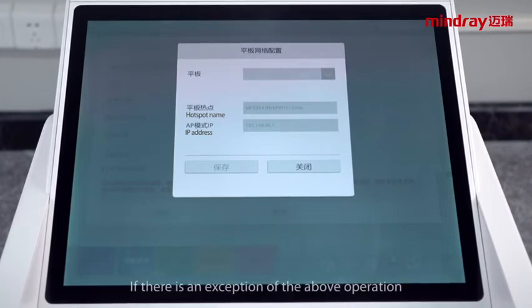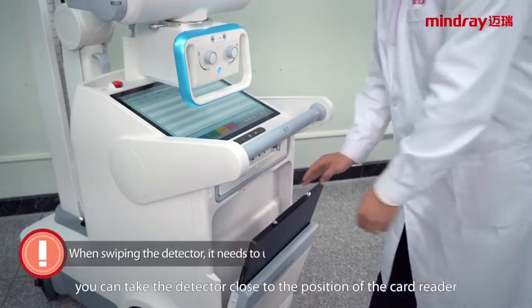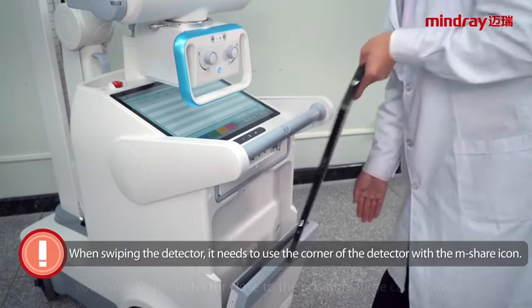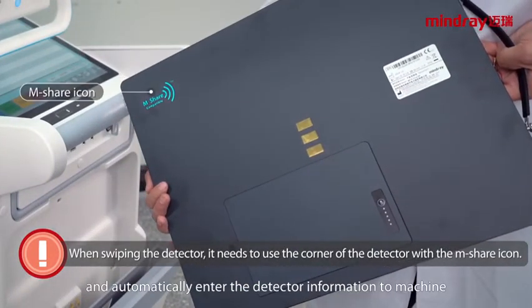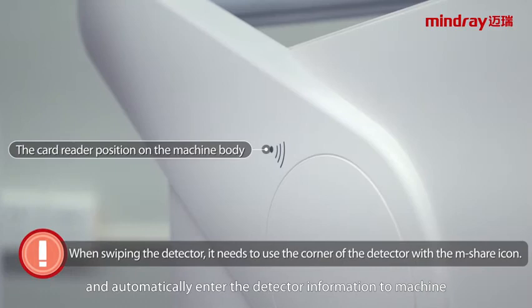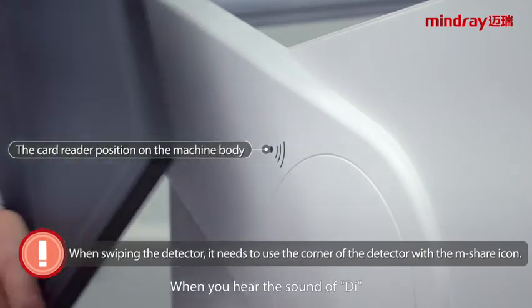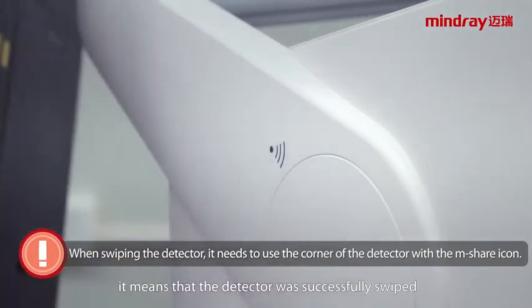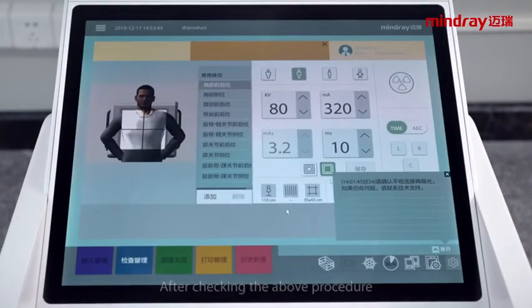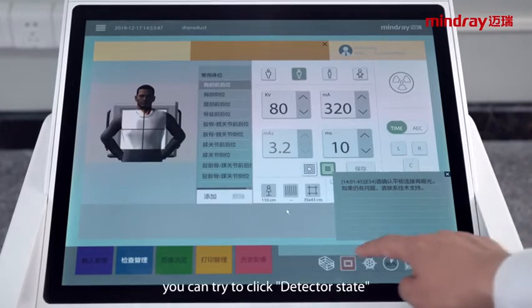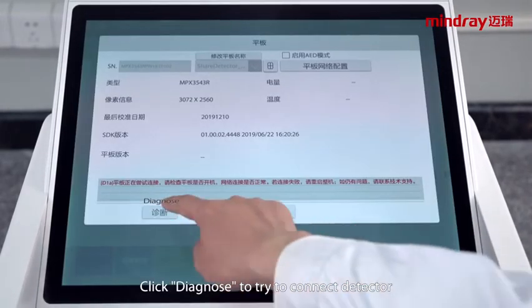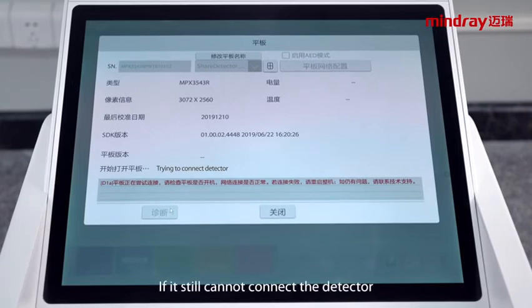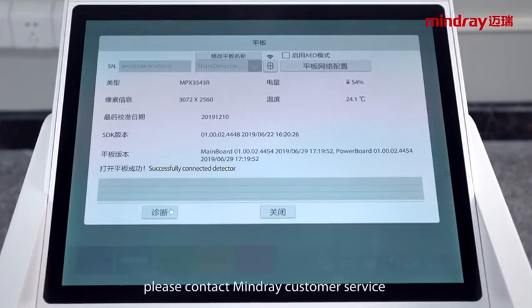192.168.96.1. If there is an exception in the above operations, you can take the detector close to the position of the card reader. Swipe the detector again and the detector information will automatically be entered into the machine. When you hear the sound of Di, it means that the detector was successfully swiped. After checking the above procedure, you can try to click Detector State. Click Diagnose to try to connect the detector. If it still cannot connect to the detector, please contact Mindray customer service.